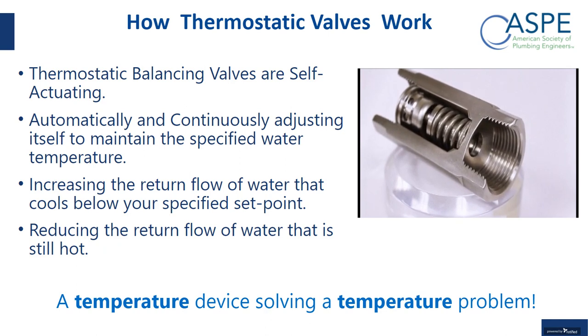It never happens. The valve always has enough bypass under any temperature conditions to make sure there's enough flow back through the pump. So let's put some numbers on it. Let's say this valve had a 120 degree Fahrenheit return temperature. So basically, on a fixed valve, it has a 10 degree Fahrenheit span.